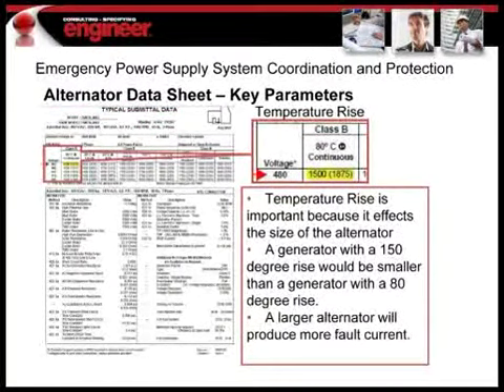The temperature rise is important because it'll affect the size of your alternator. You can specify an alternator that has, let's say, an 80-degree rise versus a 150-degree rise. Now the difference is that, let's say you had an alternator that produces 2,000 kW at 150 degrees. Well, that same alternator might produce 1,500 kW at 80 degrees. And this is all manufacturer-specific information, but you need to be aware of that because if you're specifying alternators that have a low temperature rise, you're actually going to get a bigger alternator.